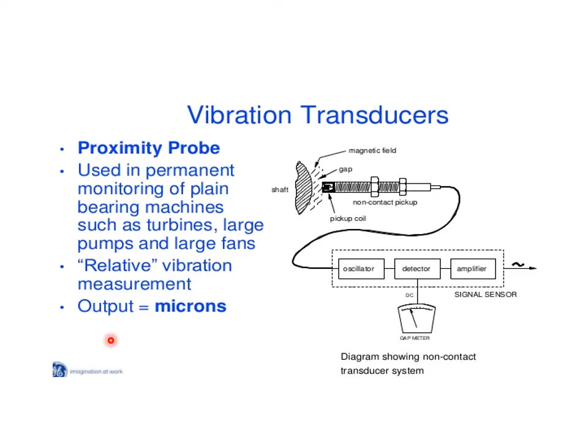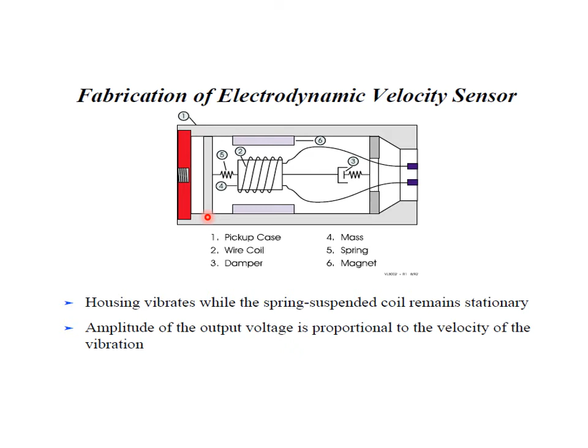This is a schematic of an electrodynamic velocity sensor. The components are: first one is a pickup case, where we are going to pick up the velocity; a wire coil; 2, a damper; mass; 5 is a spring; 6 is a magnet. This is the housing. If the housing vibrates while the spring suspended coil remains stationary, this coil part remains stationary while the housing is vibrating. The amplitude of the output voltage is proportional to the velocity of the vibration of this housing.